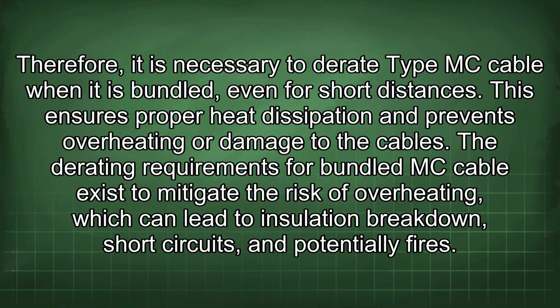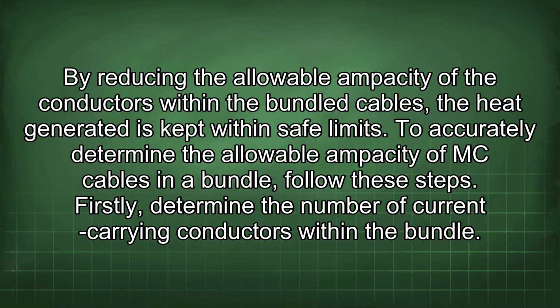The derating requirements for bundled MC cable exist to mitigate the risk of overheating, which can lead to insulation breakdown, short circuits, and potentially fires. By reducing the allowable ampacity of the conductors within the bundled cables, the heat generated is kept within safe limits.